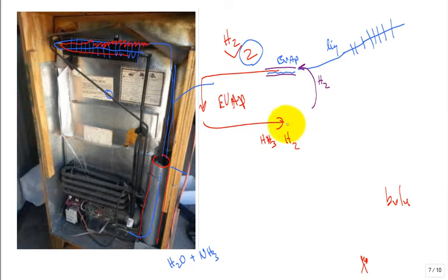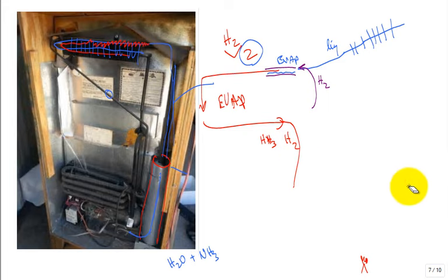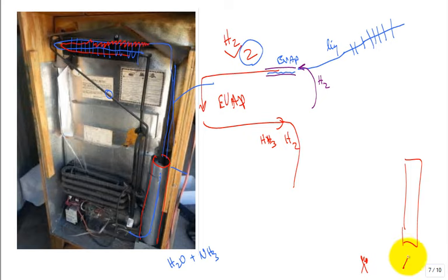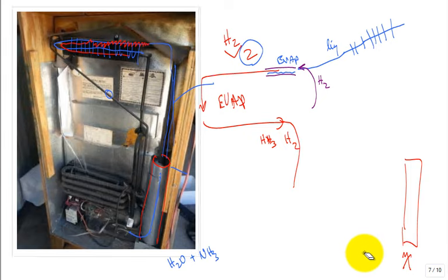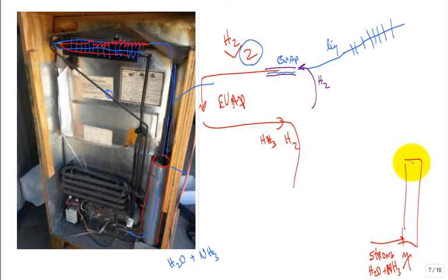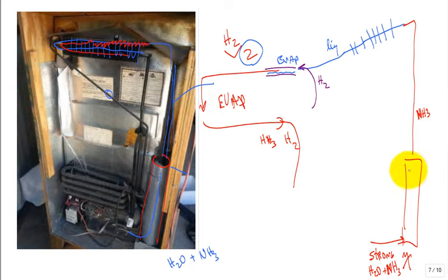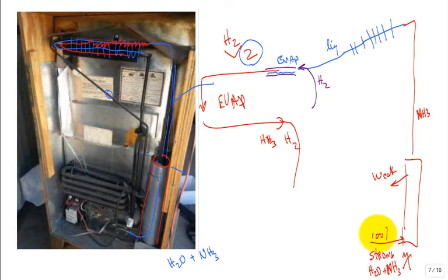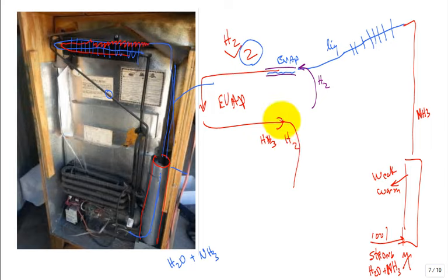What do I want to do with this? I've got to get back over here to this boiler where I'm providing the heat. I need to get a strong solution of H2O and NH3 to go up to this percolator boiler. What goes out of the percolator off the top? The weak solution—water with a little bit of ammonia still in it, but it's warm. It came in here cool and goes out hot at the top.